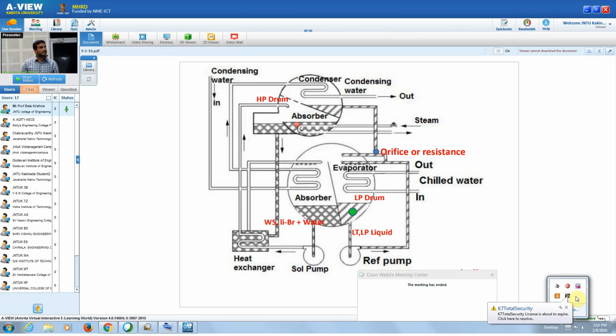See the working of this particular system. Let us start at any one particular point. We'll go for the green dot that was there in the bigger drum, the low pressure drum. At this location, the fluid will be at low temperature, low pressure. The low temperature, low pressure liquid present inside the evaporator goes into the refrigeration pump. In this particular system, you'll have evaporator, absorber, generator, condenser. In addition to this, you'll have a heat exchanger, a solution pump, and a refrigeration pump.